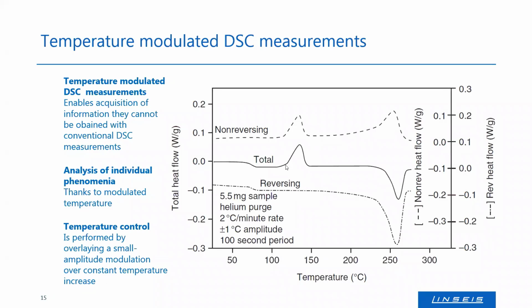But what about the rest? In the non-reversing heat flow, of course, we can see the recrystallization, but there's a second transition in the range of our melt. We cannot see this in the total heat flow, but if we check the reversing and non-reversing heat flow, in the reversing heat flow the melting peak looks much bigger than in the total heat flow. So this melting peak is overlaid by a second exothermal reaction, and this is information we can only get through this temperature modulation.